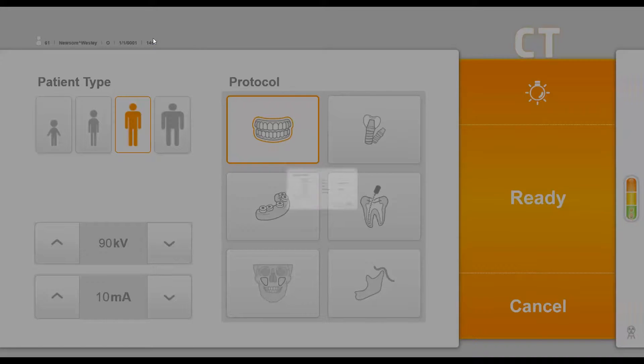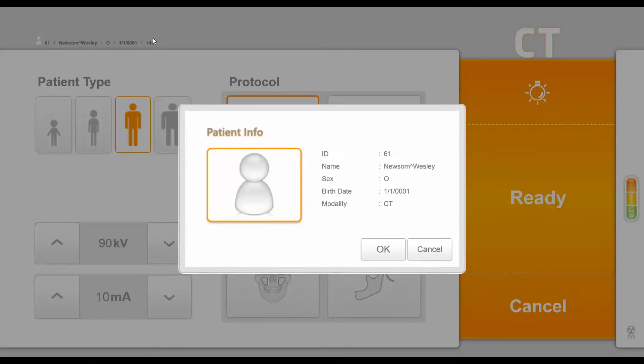Before we position our patient for the CT acquisition in the RayScan Alpha, we first want to prepare the computer. Within LED imaging software, we'll click on the RayScan CT icon. This will launch the RayScan acquisition interface for CT.